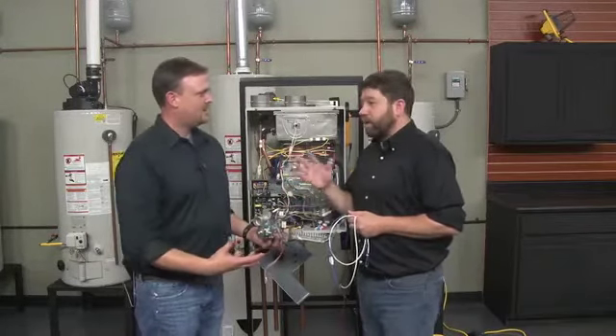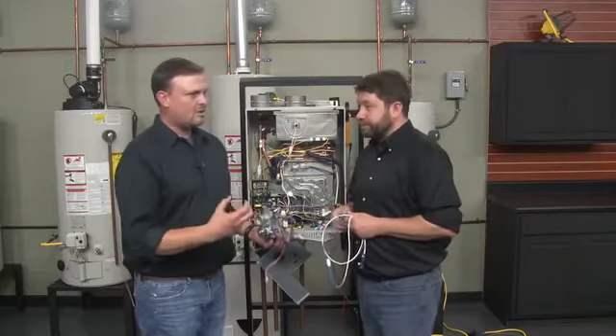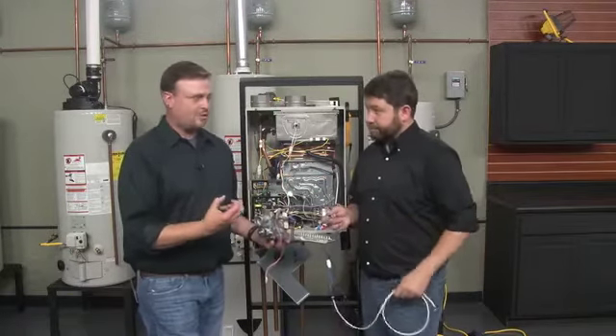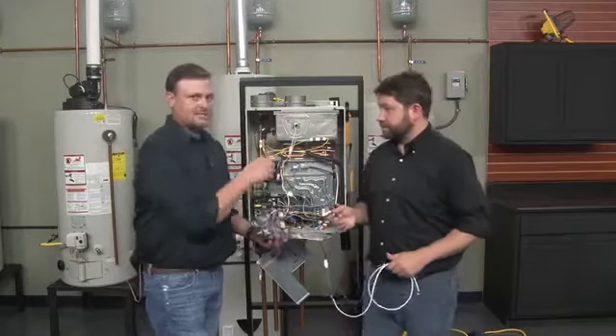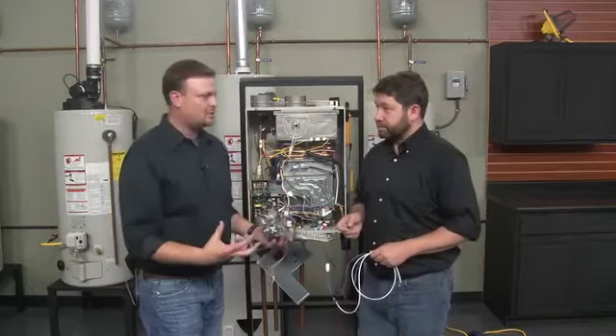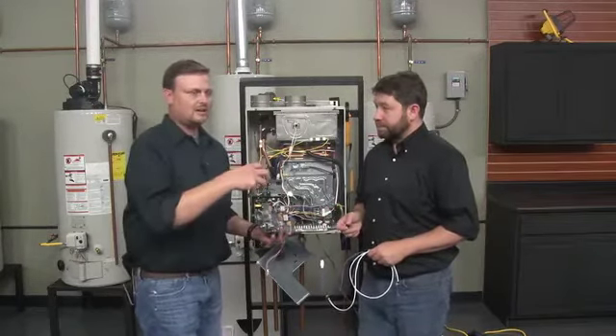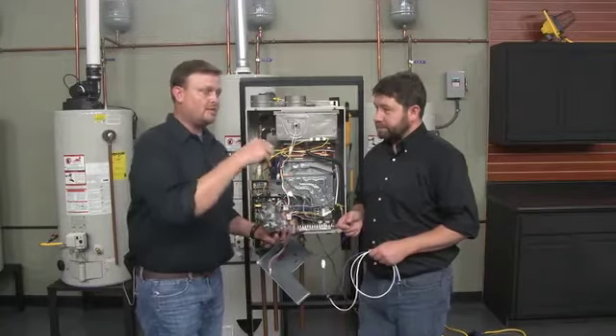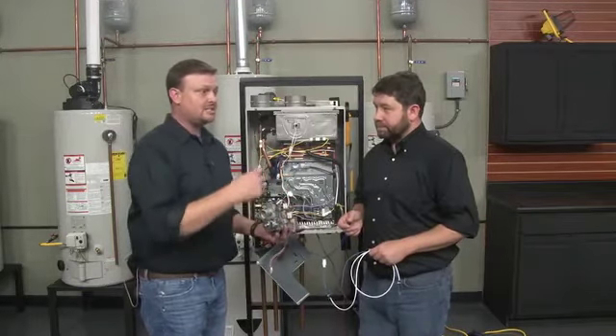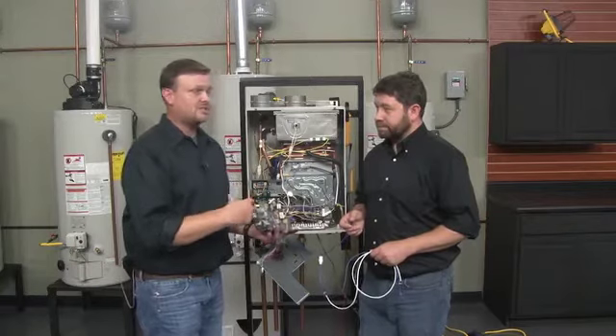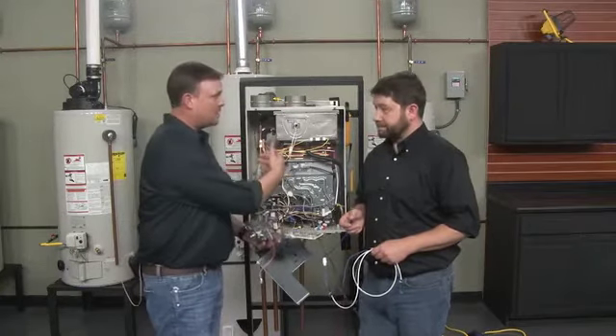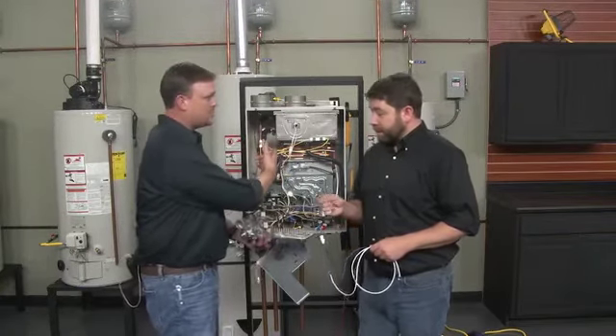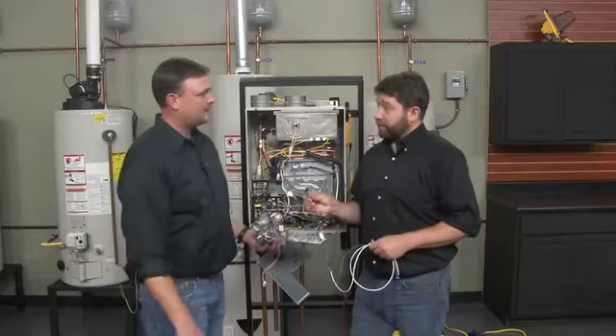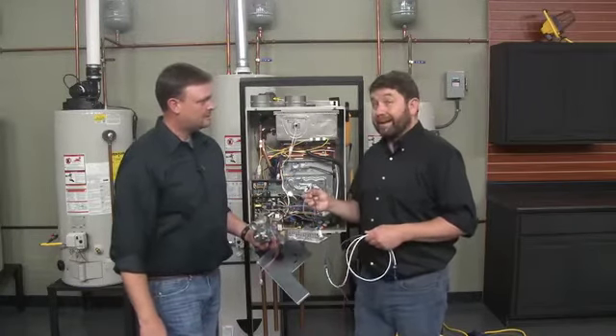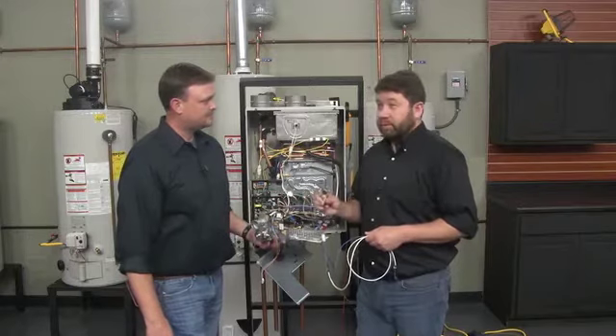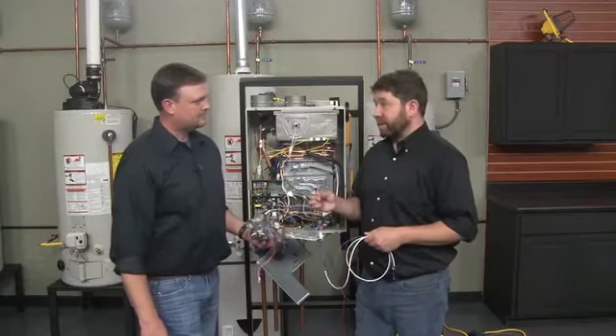There may be some other rare things, but what's going on is you're insulating that tubing with the buildup on the inside of it. So when the flame kicks on, it has to heat the buildup before it heats the water. In some cases, it's not going to be able to do that fast enough, and it's going to superheat the copper, and then we're going to hit that temperature. And what did you say that temperature was? This one is 194 degrees Fahrenheit. Now that's for the 199,000 BTU and up. The residential models are a little bit lower, at 185.